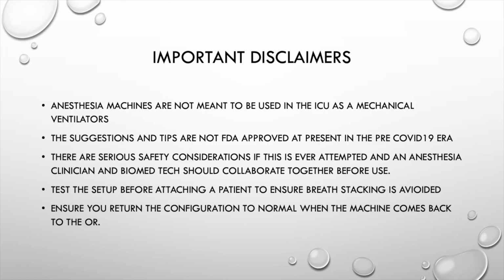Here we go. Some important disclaimers. Anesthesia machines are not meant to be used, or never were designed to be used, long term in the ICU as mechanical ventilators, so there are some key differences, which is the purpose for this overview. The suggestions and tips contained in this are not FDA approved at present, in the pre-COVID-19 era, so there are some serious safety considerations if this is ever attempted.